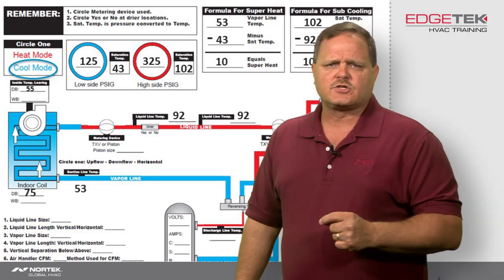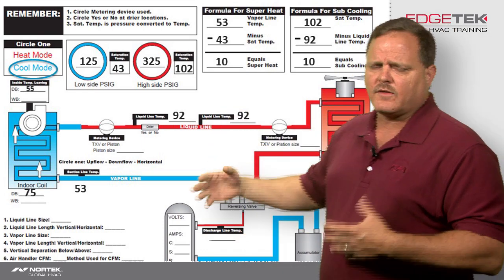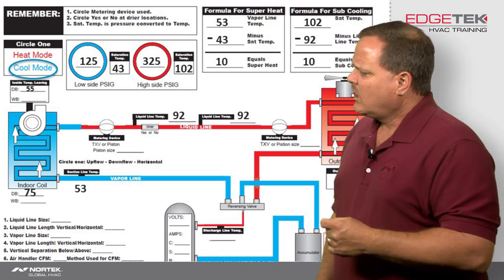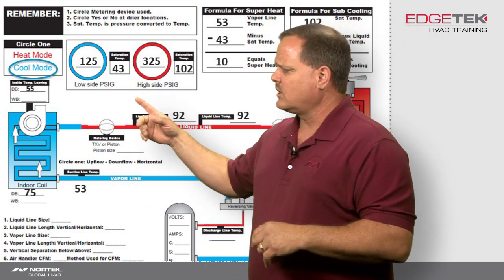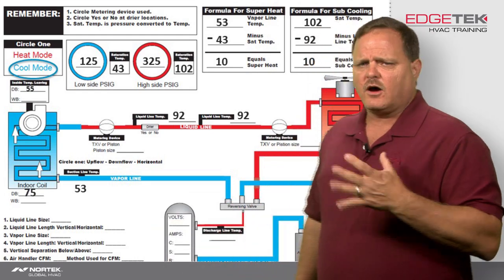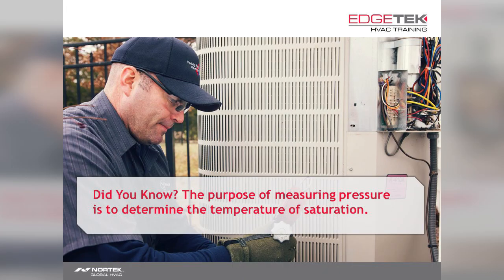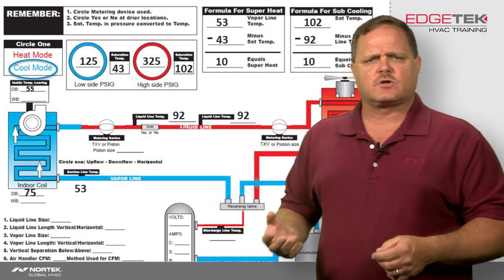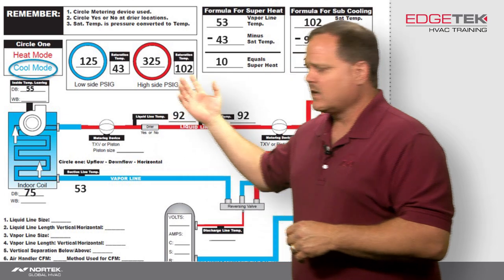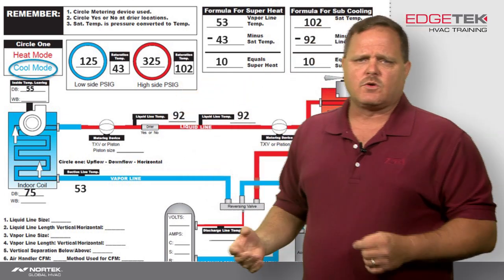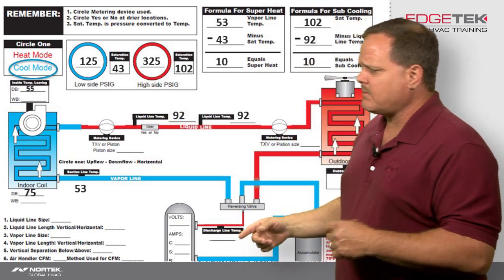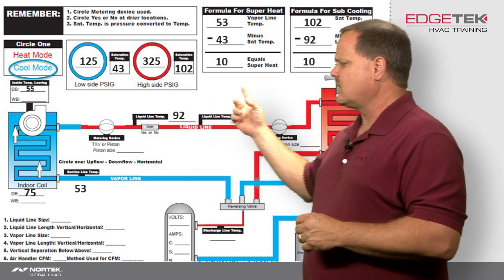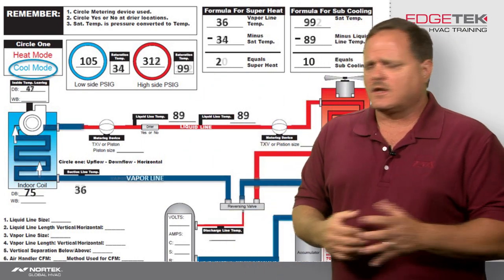You just can't ask for a system to be functioning any better than that. Where do they get the numbers — the 102 and the 43? Well, that's right off the gauges. Just use your temperature conversion chart on your gauge or a pressure-temperature chart. Keep in mind that the 43 degrees and the 102 degree condensing temperature are very important. We don't really care about the pressure so much — what we really care about is temperature. The gauge pressure is just to get you the temperature of saturation. In the condenser you're changing from a hot gas to a liquid, and in the evaporator you're changing from a liquid back into a vapor. That change of state is what we're after. Once we know that by getting our gauge readings, we can use the formulas of superheat and subcooling to determine what's going on with the system. TXVs that Nortek uses are set to 10 degrees of superheat, so this unit is working absolutely perfectly fine.